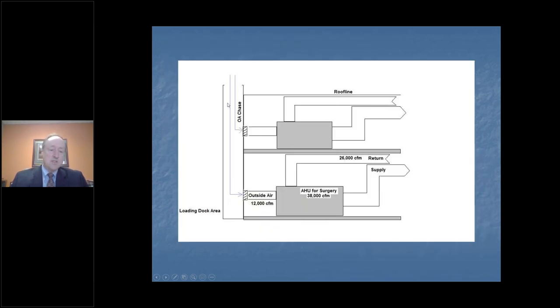So we just brought outside air in through the duct, connected it right here, and then that now served the operating rooms. From this point forward, we were able to dry this out enough, much cooler and at a much lower dew point air than even the cooling coils here. So we had dry coils from this point forward. That was great as far as not having any type of buildup on the cooling coils and much easier to maintain.